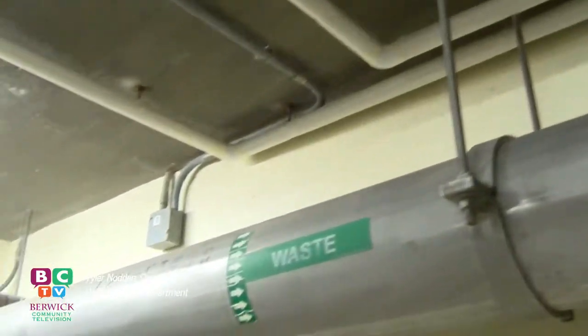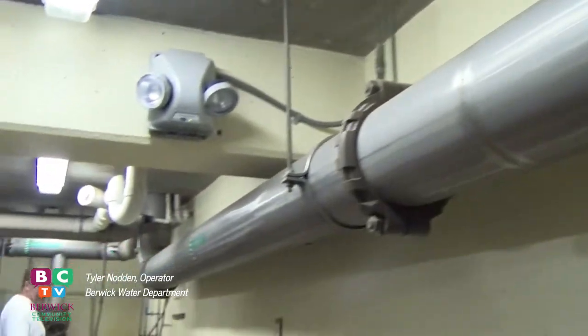These are backwash pumps. Last winter we did a total upgrade of the filters. That involved replacing the sand and anthracite layers in the filter, which has improved the operation. There was also sandblasting and painting to prolong the life of the steel filters. Time-consuming, but needed after 20 years — and it's helped us.